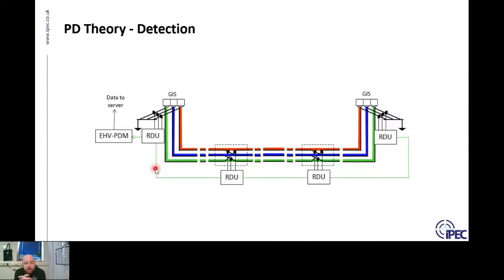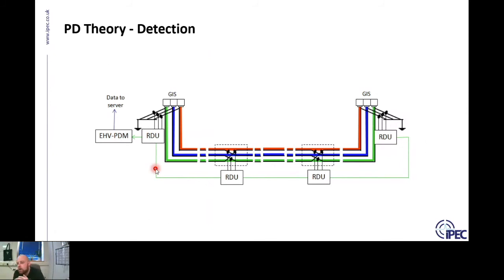People often ask how far along a cable a HFCT can detect PD. It varies and is a gray area — it depends on how large the PD is. A small PD in the early stages might not travel very far; a large PD or higher energy defect might travel much further. Depending on defect type and PD level, typically we say around four to five kilometres. In urban areas or poor earthing quality conditions that could be less; for subsea cables you can see much further.